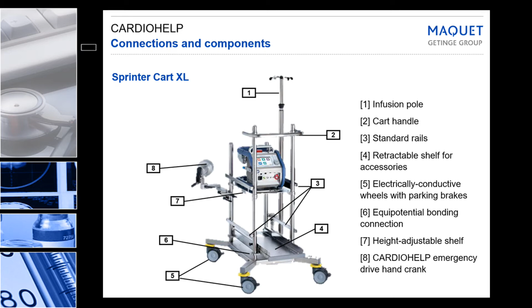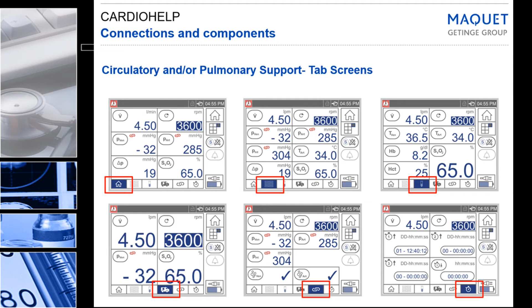This particular device has virtually all of the required monitoring and sensing capabilities that are required for the safe provision of ECMO services. There are oxygenator and pump combinations in the market that appear to be less expensive, but by the time you add all of the required sensing devices and auxiliary equipment, the price differential is significantly less. And this device is the one that is preferred by experienced ECMO centers.